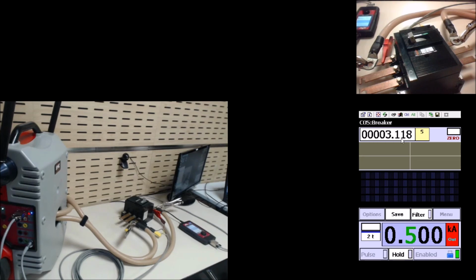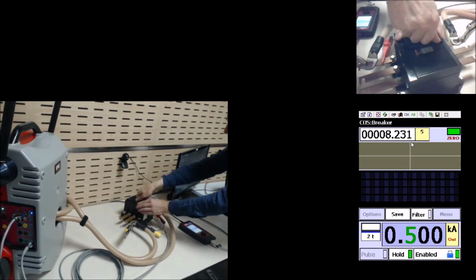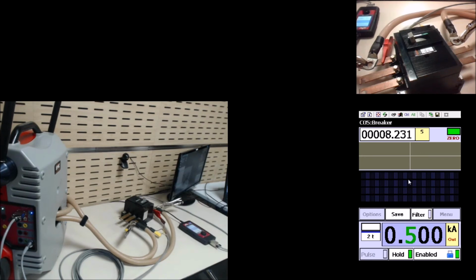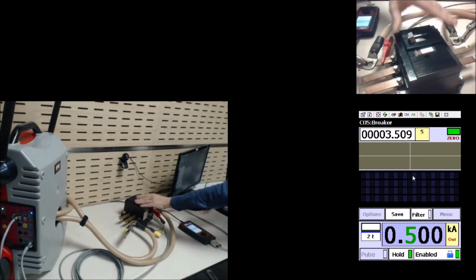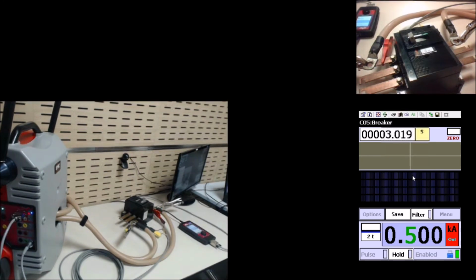So you see the chronometer also running here. We are now tripping at around 8 seconds. Let's repeat. It's obvious that the amount of heat produced at 500 ampere is sensibly higher. Let's repeat again. We are now getting steady values around 3 seconds for 500. Next value we had 800. So I will adjust 800 here now, and start.